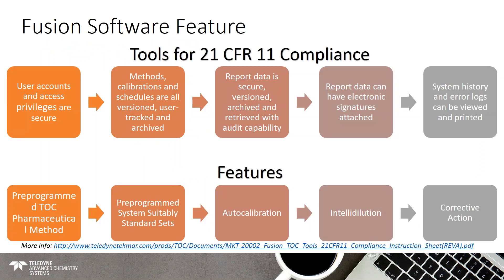The Fusion software has many tools for 21 CFR Part 11 compliance used in the pharmaceutical industry. These features include secure user accounts and access privileges requiring login. Methods, calibrations, and schedules are all versioned — if you change a method or any parameter, it will rev the version and ask you for a reason for the change. Report data is secure, versioned, archived, and retrieved with audit capabilities. There are auto-archive features so you can back up your data daily.